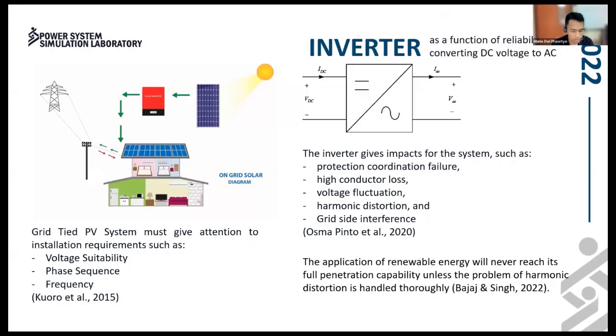Installation of a PV grid-tied system must give attention to voltage suitability, phase sequence, and frequency. So we must install inverters to reliably convert DC to AC voltage. Meanwhile, the inverter impacts the system, causing protection coordination failure, high conductor loss, voltage fluctuation, harmonic distortion, and grid-side interference.